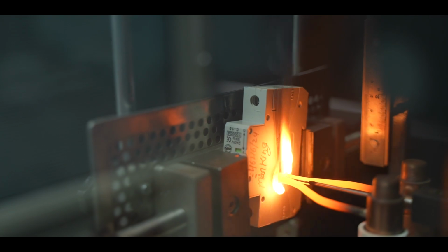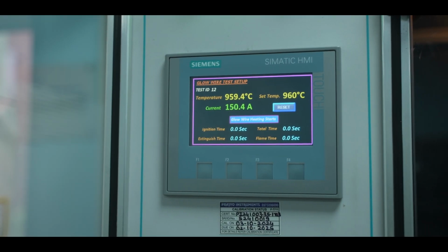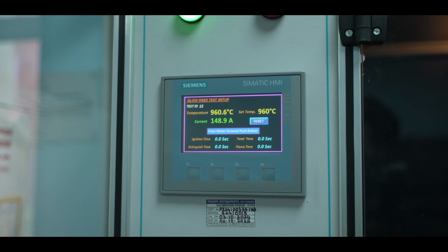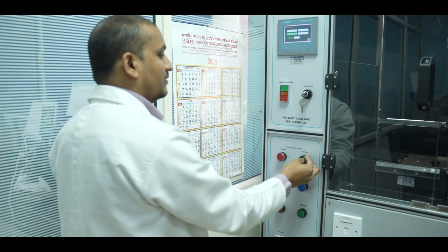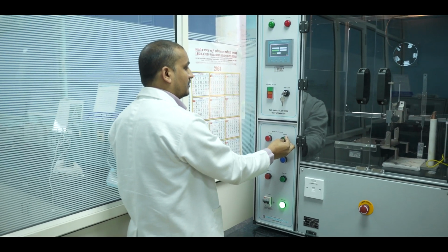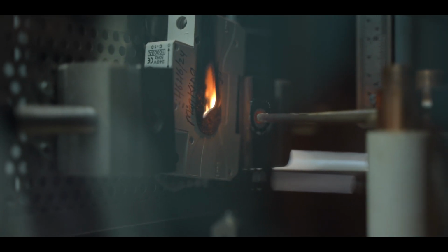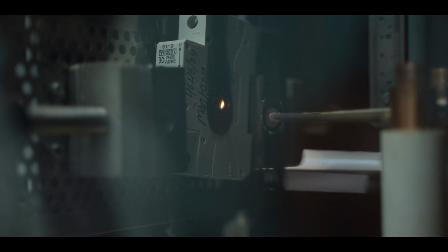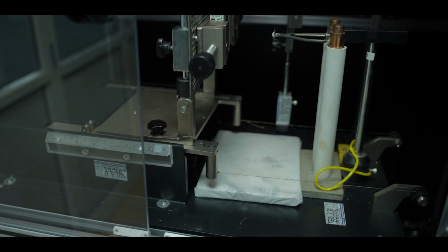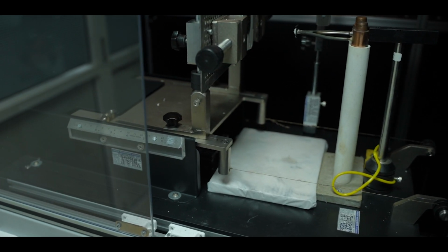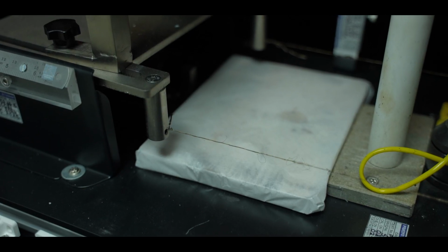Glow wire test. In this test, a heated glow wire at 960 degrees Celsius plus or minus 15 degrees Celsius is applied to the circuit breaker's insulating parts for 30 seconds. After removal, any flames or glowing must self-extinguish within 30 seconds. The test ensures no ignition of tissue paper or scorching of a pine wood board, confirming the material's safety and fire resistance.